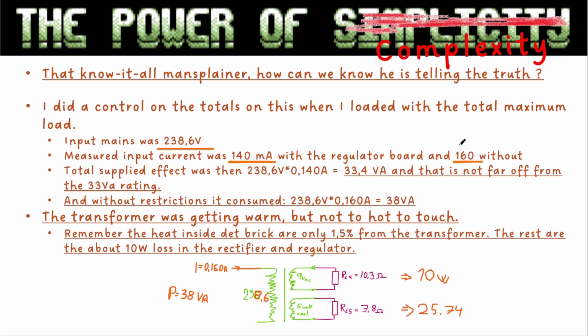This is because of the higher current draw from supplying 3.8 ohms of resistors at 10 volts instead of 5 volts. The total supplied power into the system was 33.4 volt-amps with the regulator board installed, which is not far off from the 33 volt-ampere rating. So we know this is able to supply that with no questions asked.